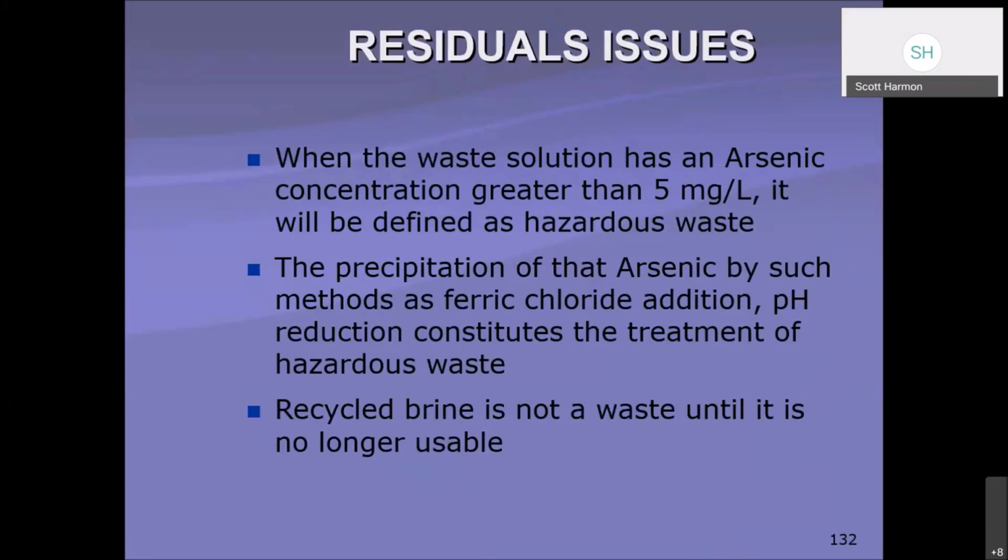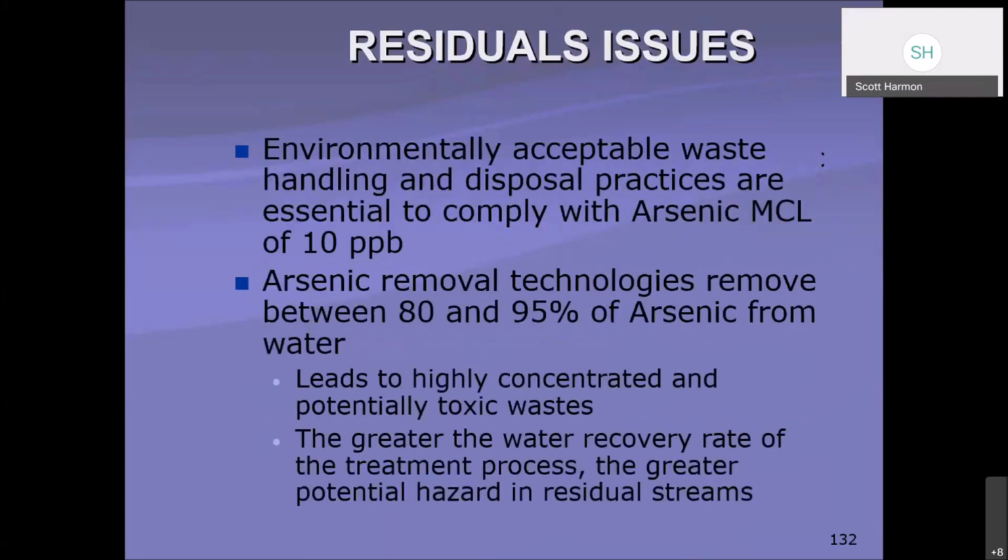There were a bunch of loopholes associated with the RCRA initially that have been filled in over time. Environmentally acceptable waste handling and disposal practices are essential to comply with the arsenic MCL of 10 parts per billion. There's a lot of innovation and technology out there on how to do that, but it is becoming increasingly harder to find land application for some of these wastes. Arsenic removal technologies remove between 80 and 90% or 95% of arsenic from water. Well, hopefully it does. In order to get it into the levels that we can send to our customers, it should.